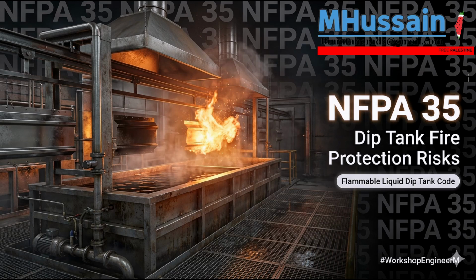This specific scenario is a notorious cause of devastating industrial fires. The standard explicitly warns against the manual dumping of powders directly into a vessel containing a class of flammable liquid. Why is this so bad? As the highly charged powder hits the surface of the flammable liquid, it can discharge a spark right at the liquid vapor interface, the absolute most dangerous place for a spark to occur. Because that's where the vapor is richest.